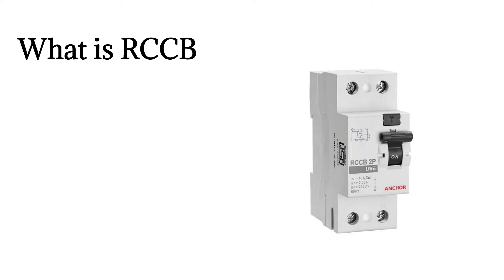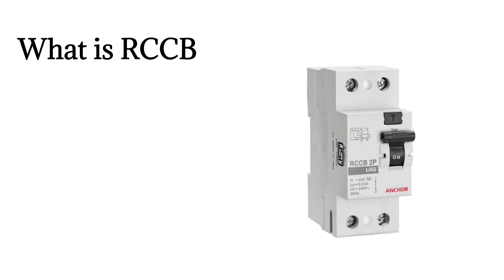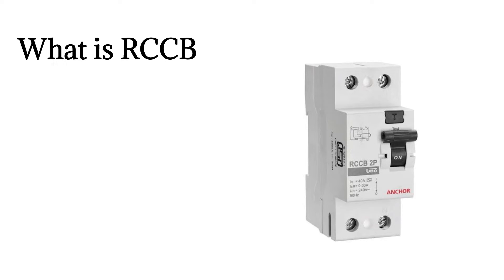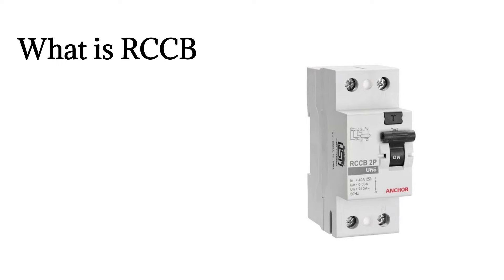RCCB stands for Residual Current Circuit Breaker. This residual current device is an electrical wiring device that disconnects the circuit whenever there is leakage of current flowing through the human body, or when the current is not balanced between the phase and neutral conductors. It is the safest device to detect and trip against electrical leakage currents, thus ensuring protection against electric shock caused by direct contacts. RCCB is generally used in series with an MCB, which protects against overcurrent and short circuit current. Both phase and neutral wires are connected through the RCCB device.